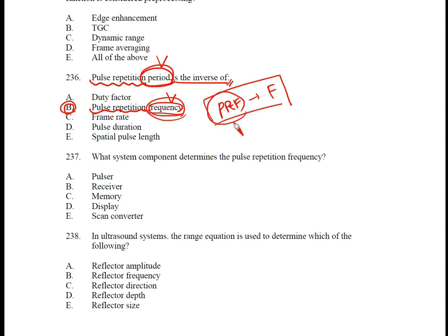To explain further, PRF refers to the concept of counting how many times a pulse is repeated. Frequency, on the other hand, refers to the concept of frequency in megahertz that we are familiar with. So even though the same terms are used, the concepts they represent are different. Therefore, if you try to connect the two in the same context, there will be points that don't make sense, so please keep that in mind.